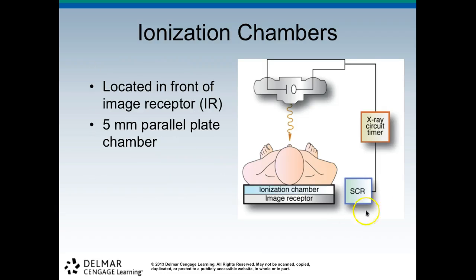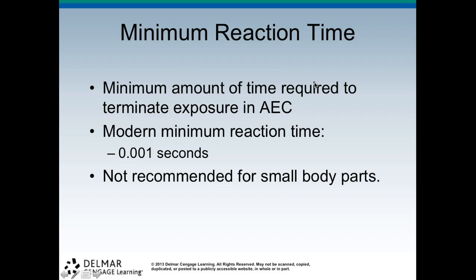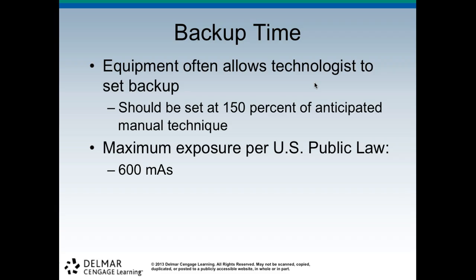So here's where they're located. You have your X-ray tube, your patient, and here's your ion chamber right there, and then your receptor. You also have a circuit from here, so it communicates to terminate the exposure. The minimum amount of time required to terminate the exposure in AEC is 0.001 seconds. So it's not recommended for small body parts, as it takes that long for it to recognize and then shut off. If you're doing a finger, it's going to be overexposed, so you have to be careful.